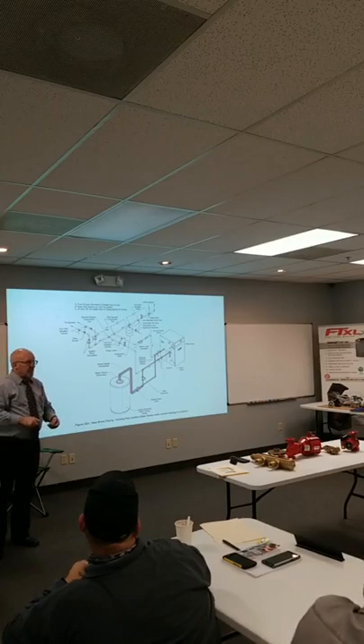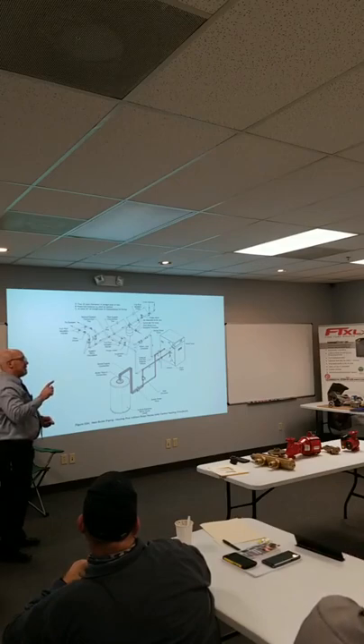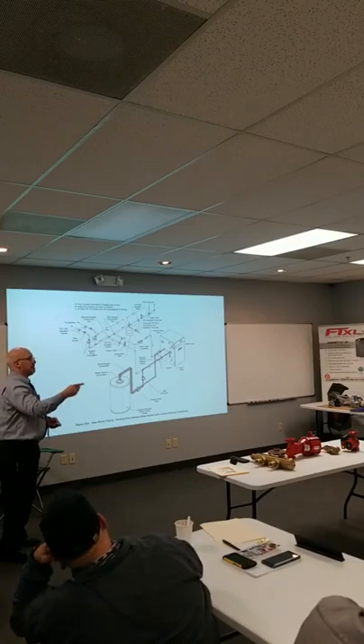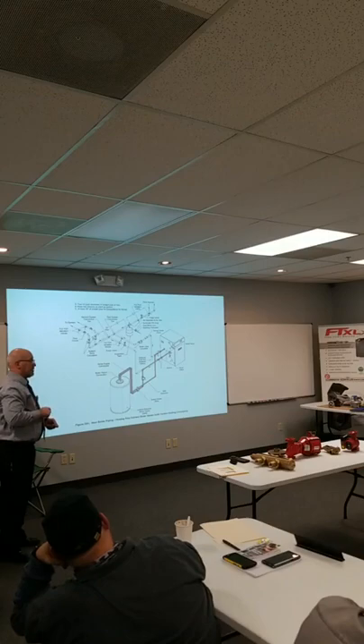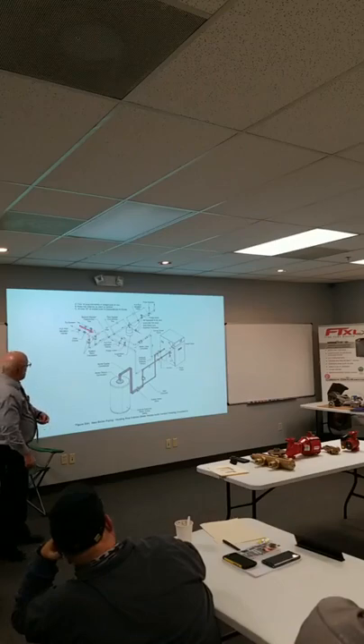It sounds like what they told this guy was to try to do some kind of pre-mixing before it comes back. So pre-mixing is not necessarily primary secondary. Pre-mixing is boiler or system bypass. And I'm wondering if that was some confusion. And there's a lot of confusion. Well, I've seen it. If you go back to your other drawing that showed the way, instead of doing your...